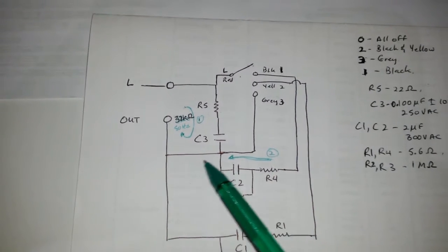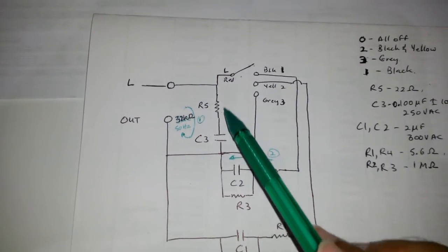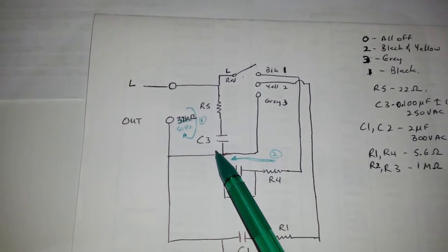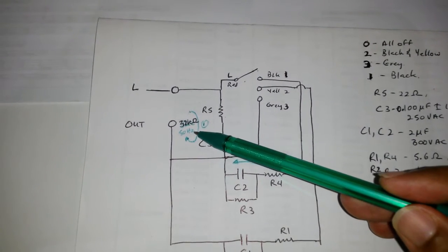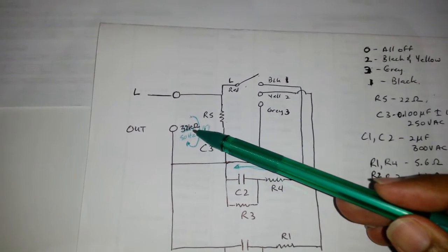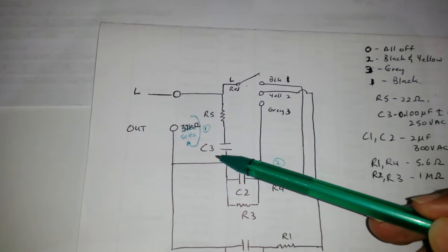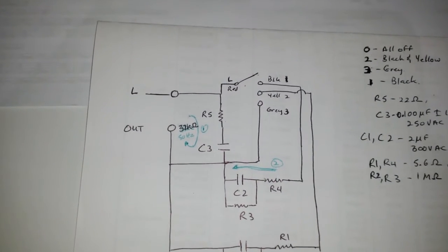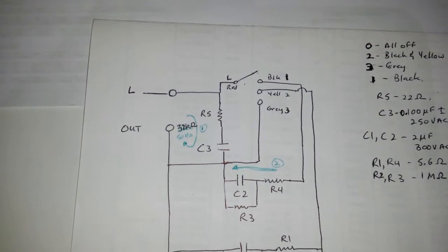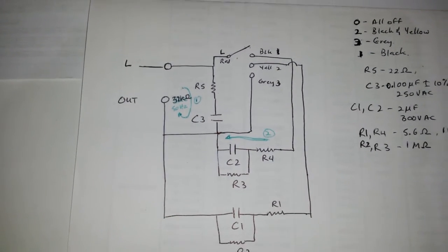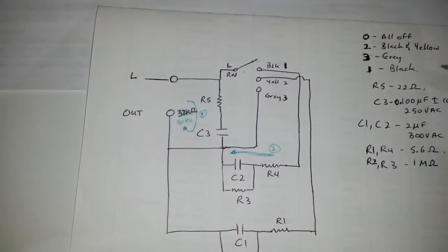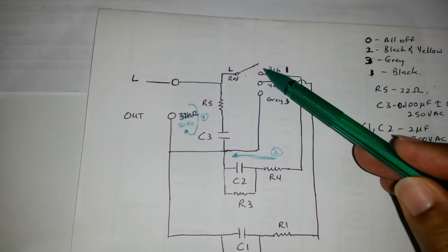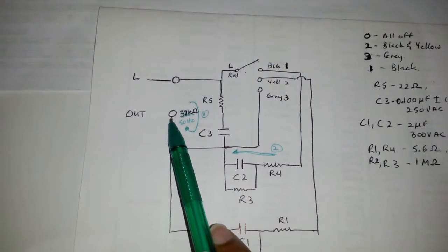This here is a snubber. What it's meant to do is under normal conditions with the 50 hertz signal, you'll get about 32 kilo-ohms here in resistance, which basically if you go to 240 volts, it's about 7.5 milliamps continuously running through this circuit.